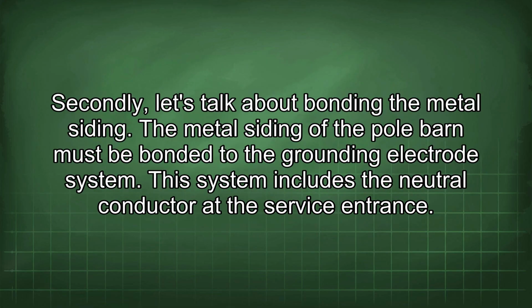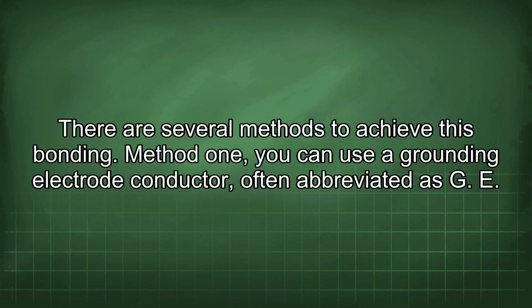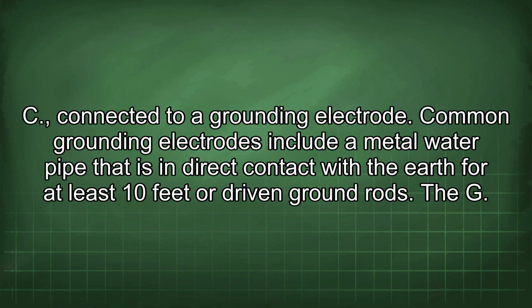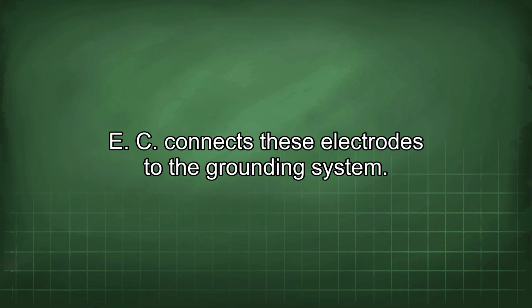Secondly, let's talk about bonding the metal siding. The metal siding of the pole barn must be bonded to the grounding electrode system. This system includes the neutral conductor at the service entrance. There are several methods to achieve this bonding. Method 1, you can use a grounding electrode conductor, often abbreviated as GEC, connected to a grounding electrode. Common grounding electrodes include a metal water pipe that is in direct contact with the earth for at least 10 feet or driven ground rods. The GEC connects these electrodes to the grounding system.